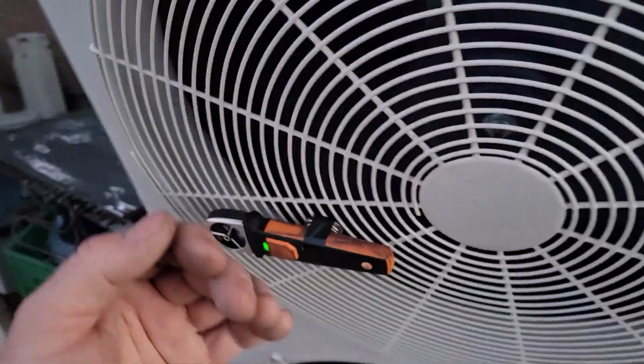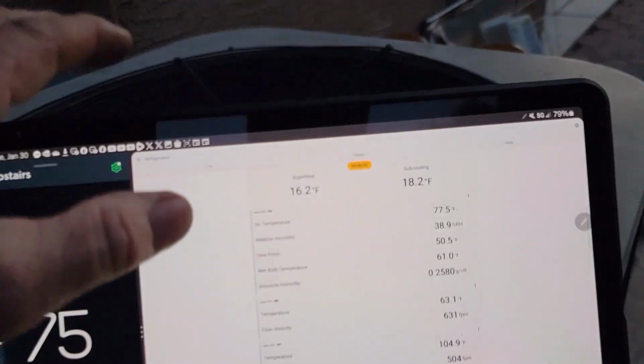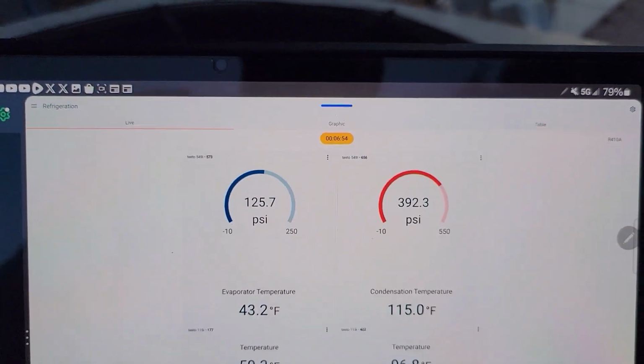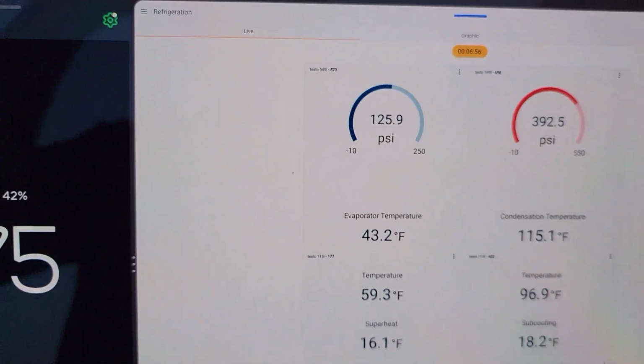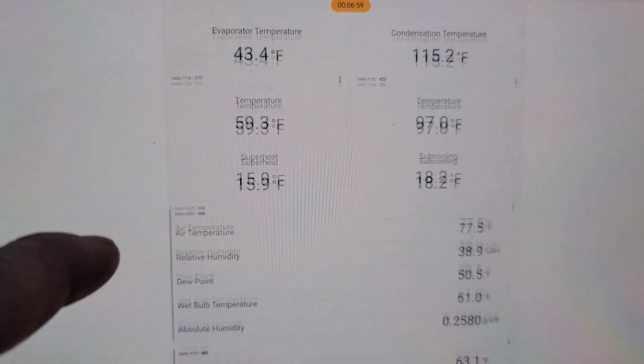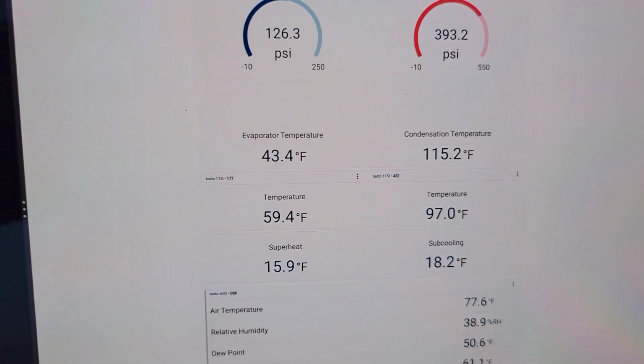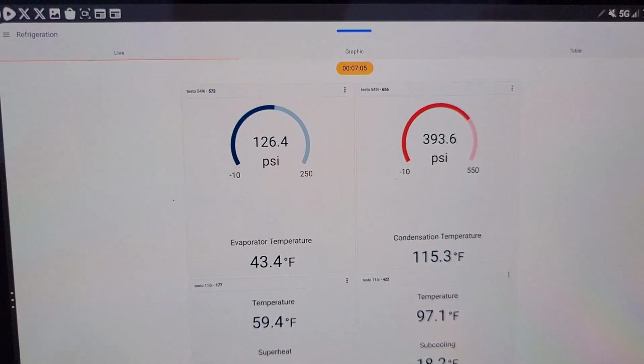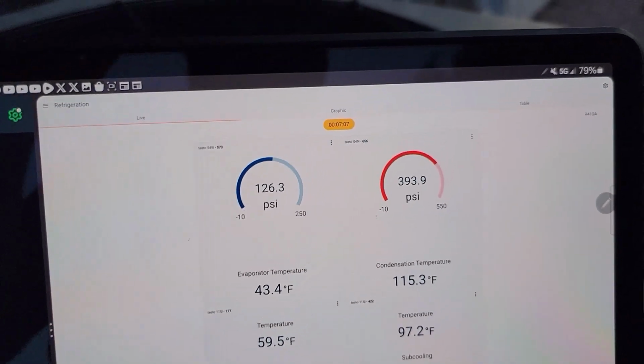Alright, so this feels colder and colder. Let's get a final reading. 392, 125, because it's kind of warm out. 16 degrees superheat, 18 subcooling. Can't really go by that in heating mode as much. But you can see those capillary tubes that I put in there. Some people kind of gave me the stink eye for that.